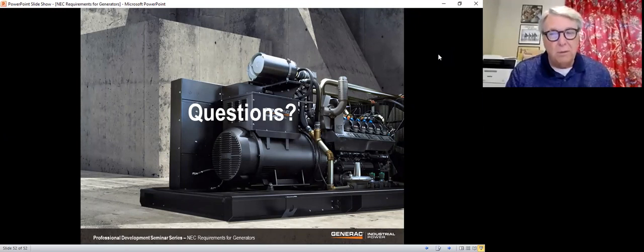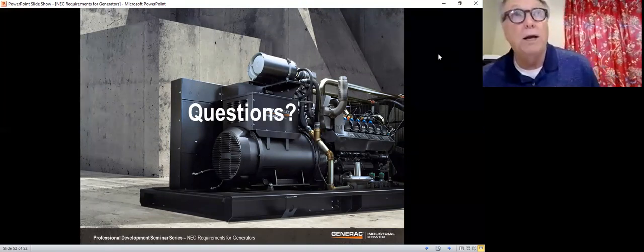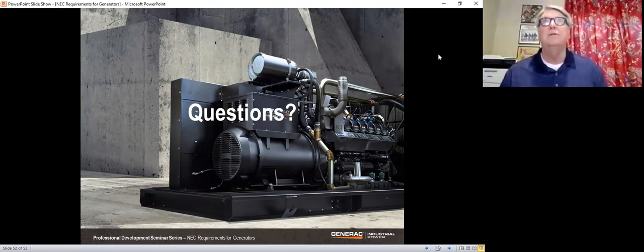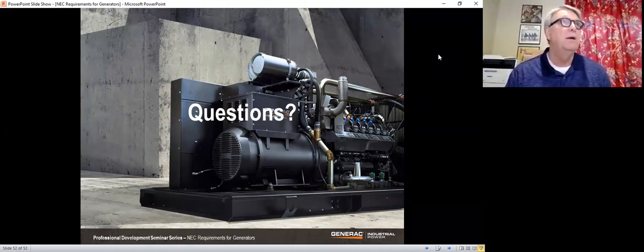So you kind of have to know a little bit about this in order to make sure that your spec's okay. One other thing you can do, well, two things you can do, but they're related: if you use our sizing program, after you size the generator, it has a way where you can download a typical spec. And then you can just go through that spec and read it and make sure that it says what you want it to. And in many cases, it'll have some choices in there where you need to make a choice. The last thing to do, which we would recommend, is call somebody you trust in the generator industry. We think that we would be a good choice for that, and say, hey, I've got a spec and it's for this generator. Would you mind taking a look at it and letting me know if there's anything in there that I've missed? We do that all the time, and so we're happy to do that.